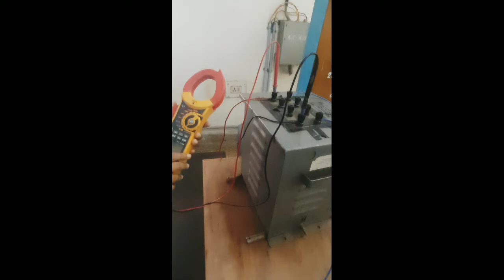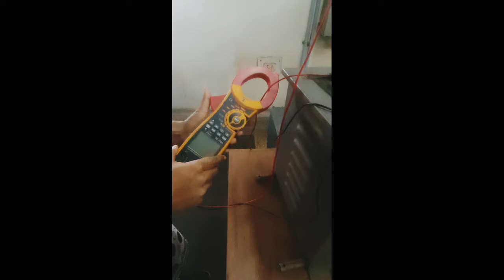In the procedure, we have switched on the transformer and connected the probes of the clamp meter across the primary. First we will measure the wattage reading on the primary side with no load, when the secondary is not connected. We have taken the mode to power, and the primary side reading is 0.04 kilowatts. It is in no load condition, so that is the reading from the primary side.